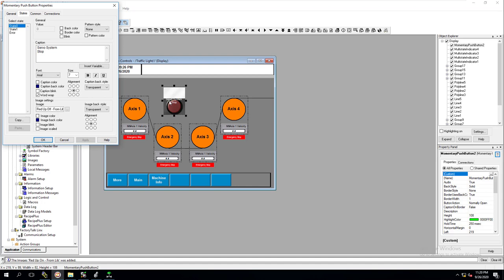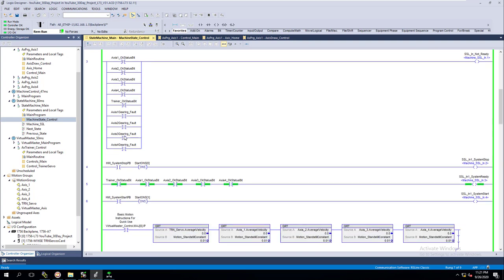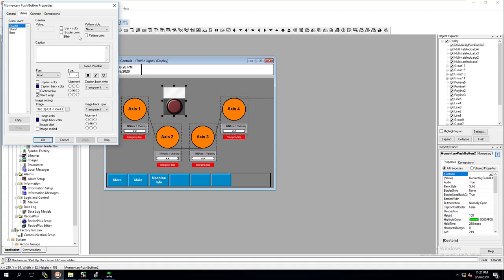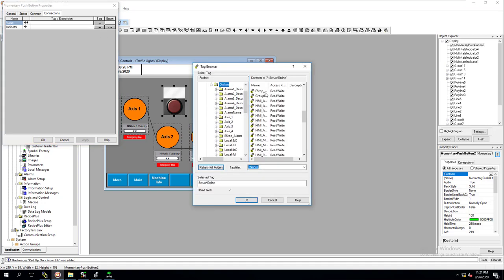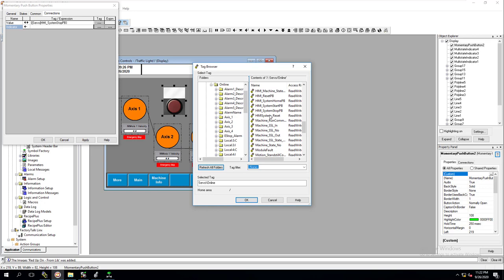See if we can get the sizing right and see how it actually comes in. That's somewhat of the problem here, which is kind of why I wanted to show that — because what you want to do is not use this and just use the button illuminated. Now we have the two indicators. We need to have the actual system start. So what tag are we going to be looking for? We need to go into our controls and look for our system start. We have HMI system stop and start — that's basically what we're looking for. So let's come in and tag this with the HMI. This is a stop push button and the indicator is going to be a stop push button. So this is kind of easier — easy to throw in there. Stop push button again.